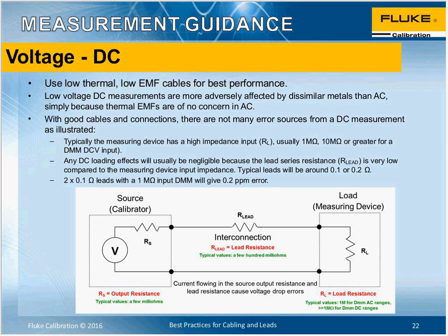Thank you. It was a good question, and somebody caught on to this. The question was, is there an order that's followed when performing electrical calibration? The reason we mentioned DC first is that it's common to do the DC calibration of a DMM or a device first, because many of the circuits that operate inside the calibrator are DC circuitry, so it's good to make sure that's in check first. The calibration manuals for each device vary, but typically DC is started with.